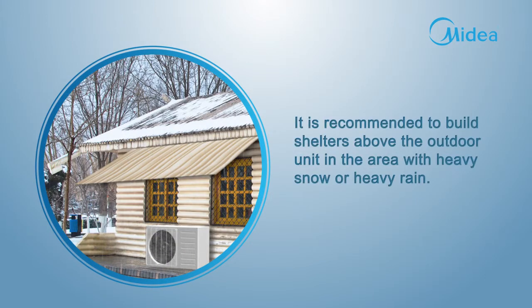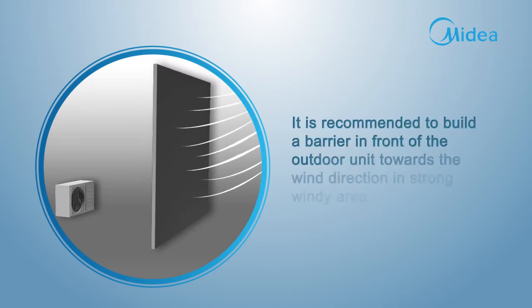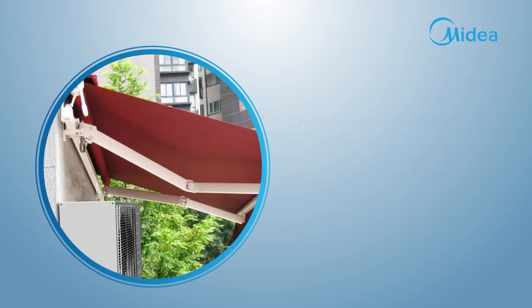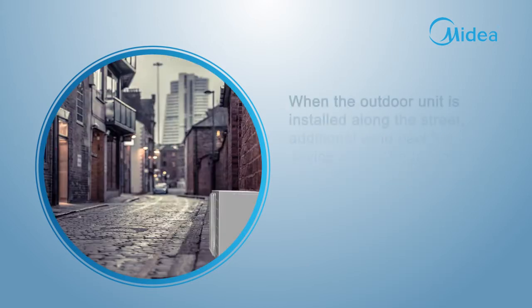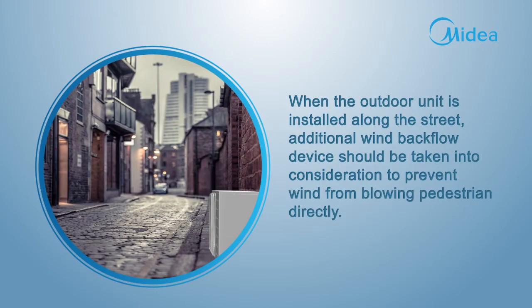It is recommended to build shelters above the outdoor unit in areas with heavy snow or heavy rain. Build a barrier in front of the outdoor unit towards the wind direction in strong windy areas. Choose a position with good ventilation but sheltered from rain and direct sun exposure if possible. When the outdoor unit is installed along the street, an additional wind backflow device should be considered to prevent wind from blowing pedestrians directly.